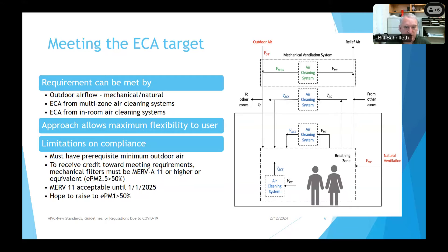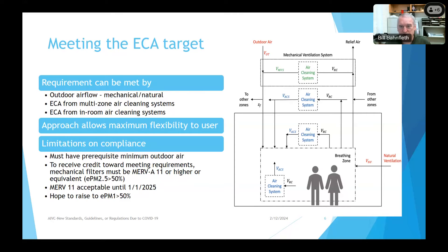There are only a few limitations on compliance. One is that you must maintain minimum outdoor air — whatever standard applies locally remains in force, determining minimum filter efficiencies and minimum outdoor air. We've also specified that if applying the standard prescriptively and taking credit for air recirculated through a filter, that filter must be a MERV A11 or equivalently an EPM 2.5 greater-than-50% filter. This ensures good filter life and reliable performance at end of filter life. Because not many filters are rated by the MERV A rating — which conditions the filter to remove electrostatic charge — this requirement is not enforced until January 2025.